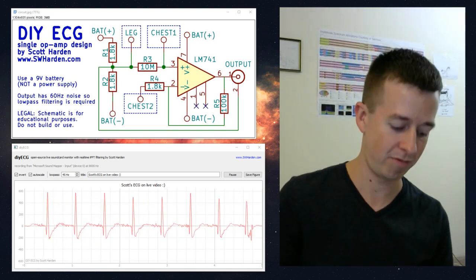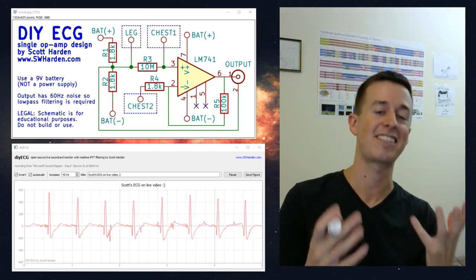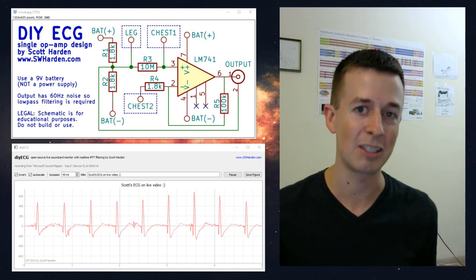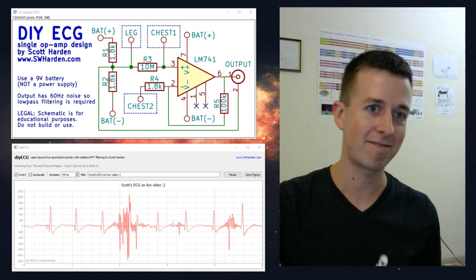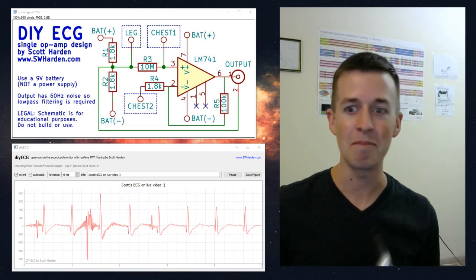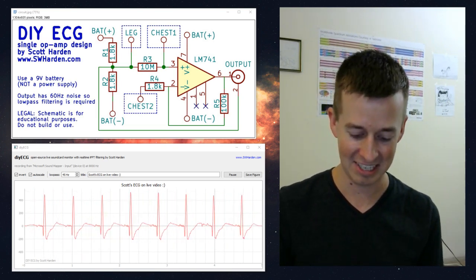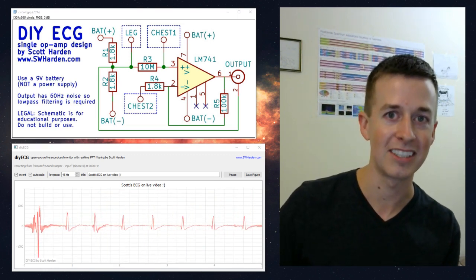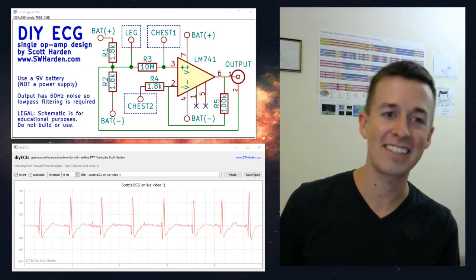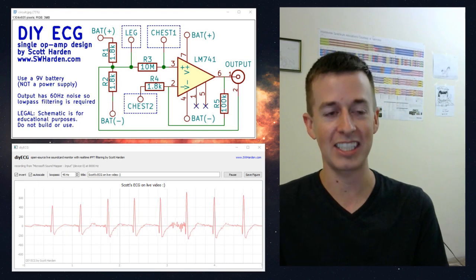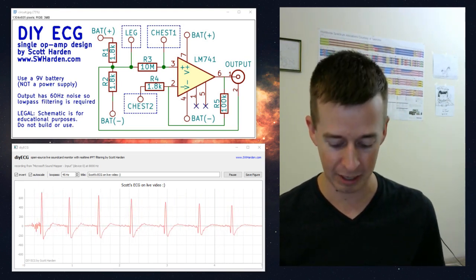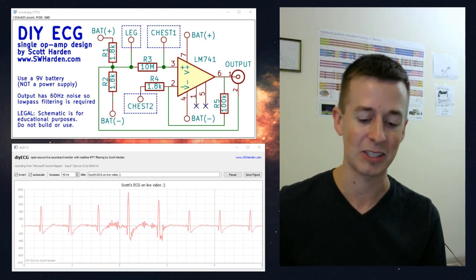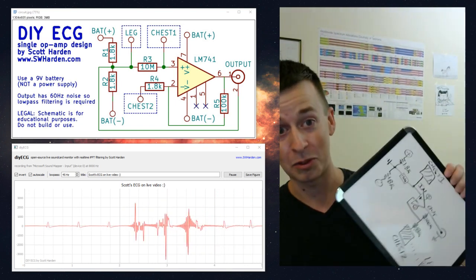It's very easy when we talk about the safety of an ECG machine like this. A lot of people can come out and say, oh my gosh, this is dangerous. And this is why. This, this, and this. And it was actually really interesting. In the past, when I posted similar projects, I get a lot of feedback. Kind of, you know, in both directions. Some people say that it's meaningless, small voltages and currents and are sort of proposing that it's extremely safe. And some people that are truly concerned about dying because they point out the fact, which is true, that milliamps of current can kill, especially if they're oscillated in a certain way. And I've also heard some people equate it to putting headphones in their ear and say they're getting about the same amount of electrical current from that.